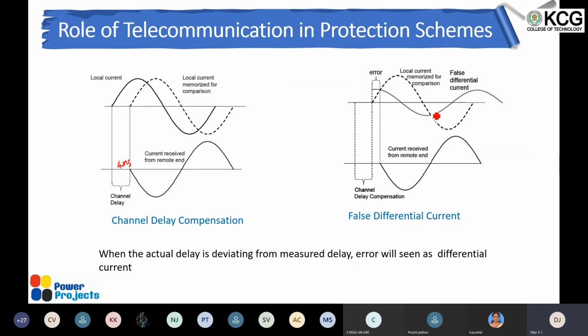So that's spurious tripping, because the difference between the communication channel delay adopted in the relay and the actual delay causes a resultant current in the relay calculation, which can lead to spurious tripping of the circuit breakers. So it needs to be avoided. That's why the physical, cyber security issue comes in here. If somebody does something in the communication network, it's going to affect the entire protection system. So yeah, that was for the differential protection.